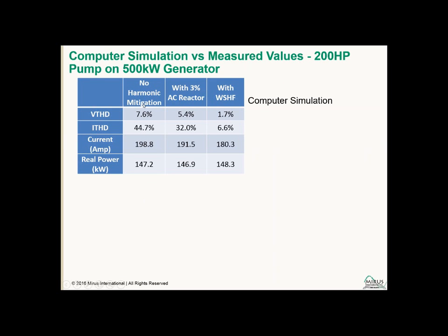So if we look and compare the three simulations, on the 500 kilowatt generator with no harmonic mitigation, we have 7.6% voltage distortion. When we add the line reactor, voltage distortion drops to 5.4. With the filter, it drops to 1.7. You can see the reason the voltage distortion drops is that the current distortion is dropping as we remove the harmonic content.